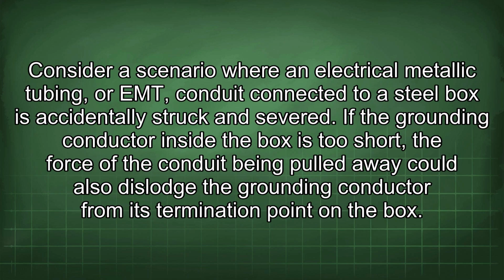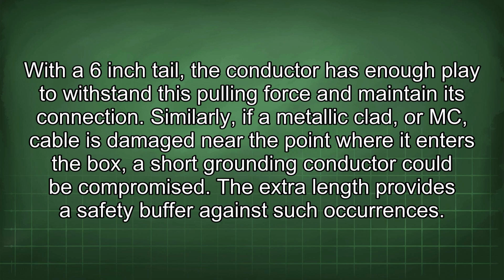Consider a scenario where an electrical metallic tubing or EMT conduit connected to a steel box is accidentally struck and severed. If the grounding conductor inside the box is too short, the force of the conduit being pulled away could also dislodge the grounding conductor from its termination point in the box. With a 6-inch tail, the conductor has enough play to withstand this pulling force and maintain its connection. Similarly, if a metallic-clad, or MC, cable is damaged near the point where it enters the box, a short grounding conductor could be compromised. The extra length provides a safety buffer against such occurrences.